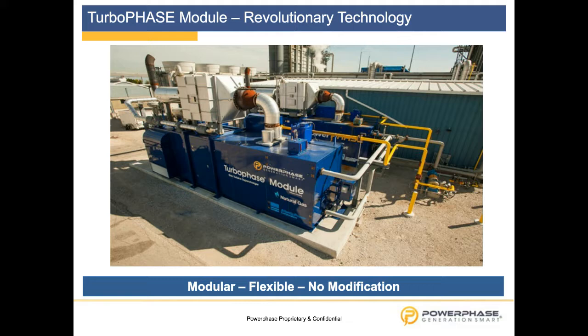This is actually showing two of the Turbophase modules. It is a 40-feet container that is modular, and it's scalable to the size of each gas turbine. The module itself is always on the same dimensions based on the gas turbine size. It is just scalable up to 8 modules, for example. That is simply caused by the fact that bigger gas turbines have a higher mass flow, and we want to account with our dry air injection for a maximum of 5% of the main mass flow produced by the gas turbine compressor.